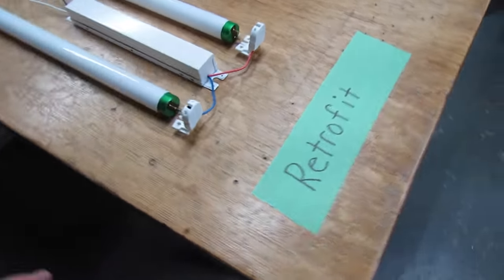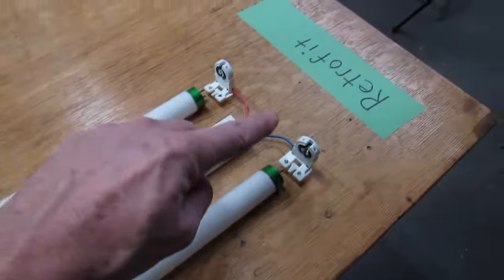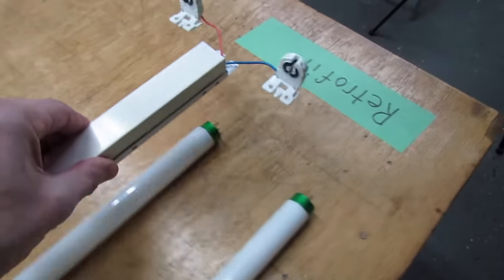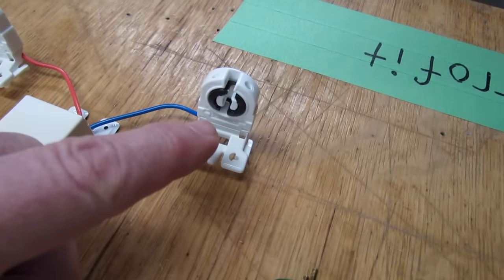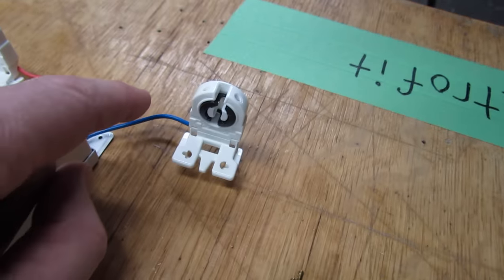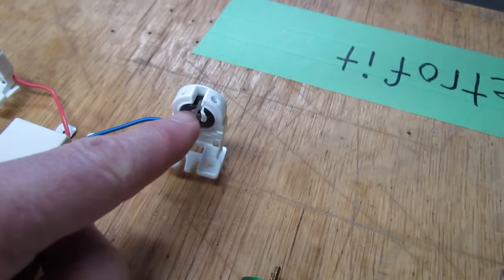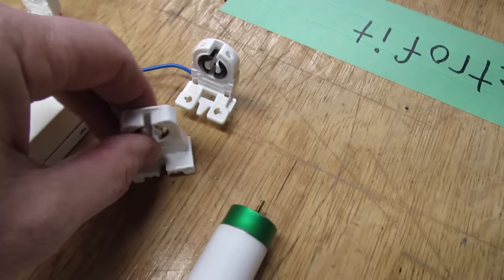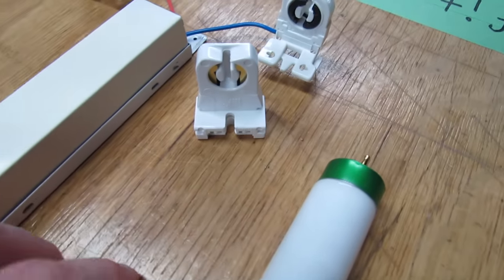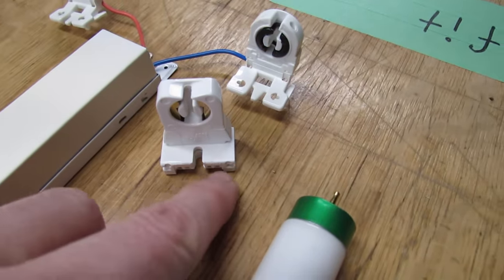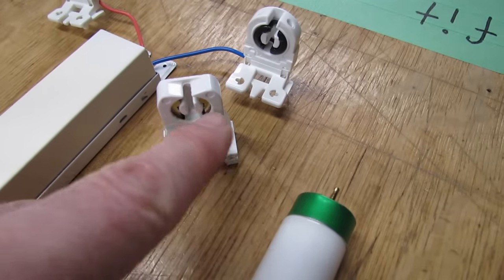When you do a retrofit, you remove the ballast and the connectors at the end because you don't need them anymore. These connectors are called shunted—they have one wire going to both terminals. You'll replace them with non-shunted connectors, which have a circuit going to each side of the terminals.